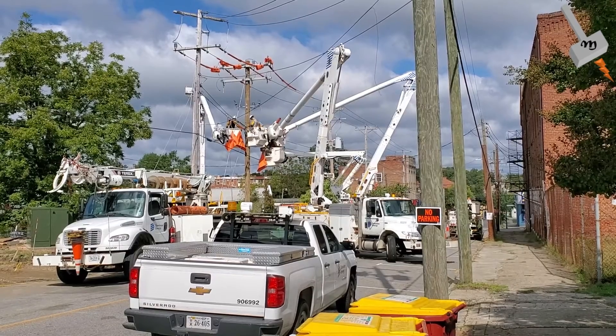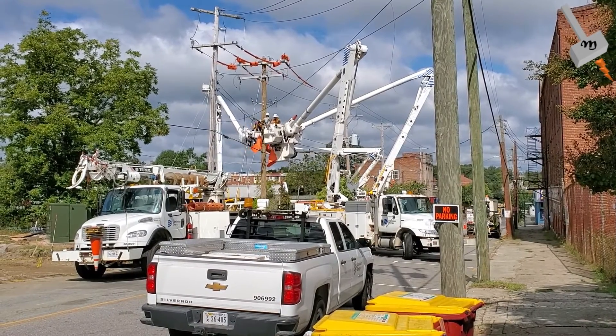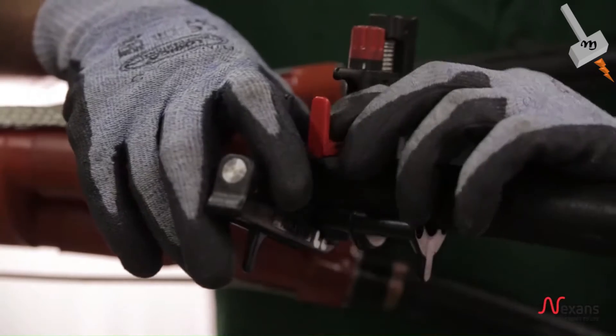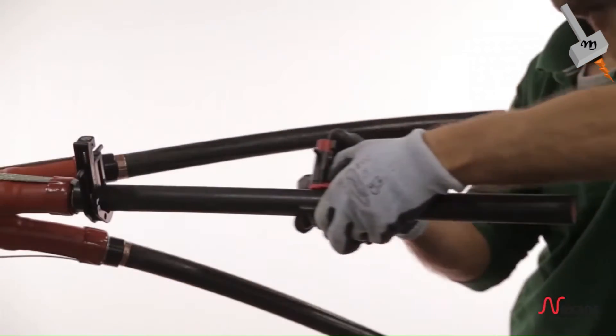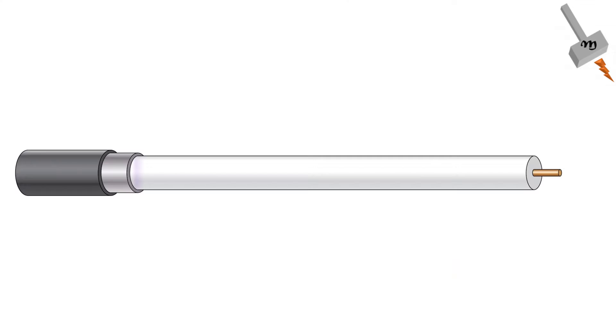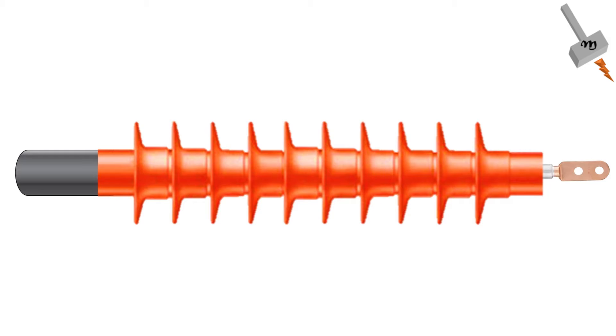In this video, the terms HV and MV are used interchangeably and refer to cables that are shielded in some fashion. A shielded cable has uniform electrical field density along the axis, but the field itself varies in the radial direction. When an HV cable needs to be connected to equipment, the grounded shield needs to be stripped back, which distorts the symmetrical electric field distribution. Electric field tends to concentrate at the edge of shield discontinuity and will eventually overstress and damage the cable insulation. Cable terminations help manage the electric field stress on the insulation and hence prevent premature cable damage.